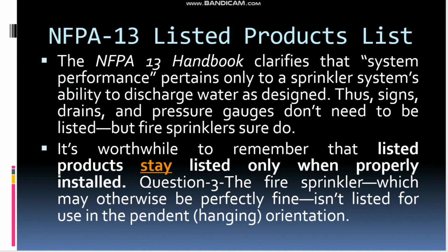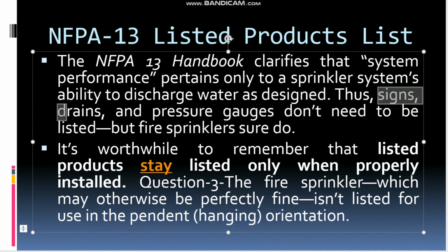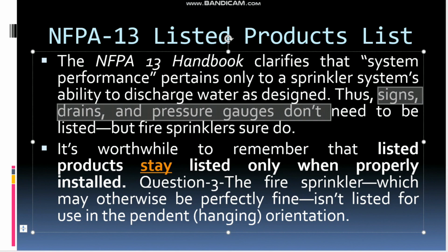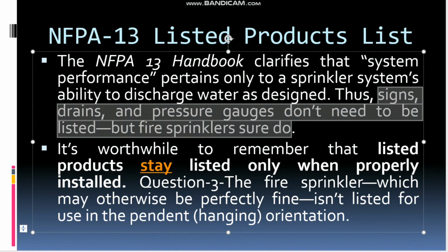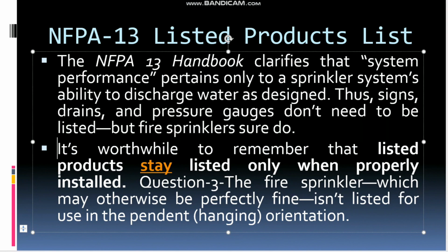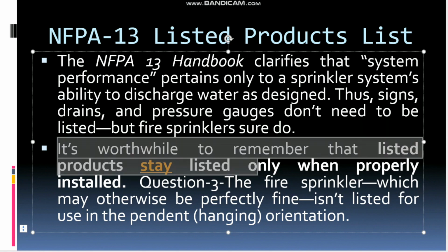As per the last comment, whatever is not affecting the system performance, there is no need to have the listing. For example, here the warning signs, the drain connection and the pressure gauge don't need to be listed, but fire sprinklers surely should be, because they affect the performance of the system. Also, it is important to note that listed products stay listed only when properly installed.